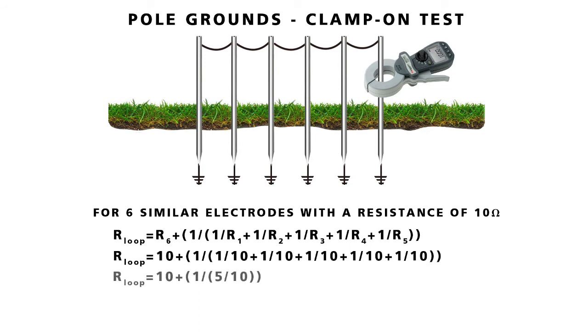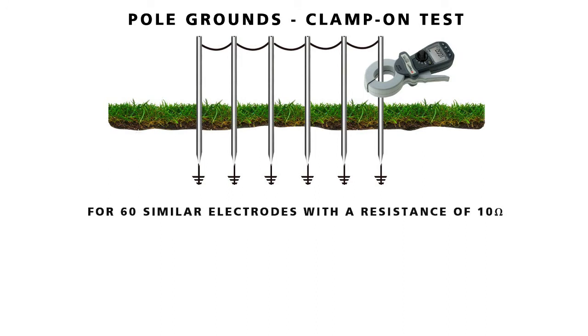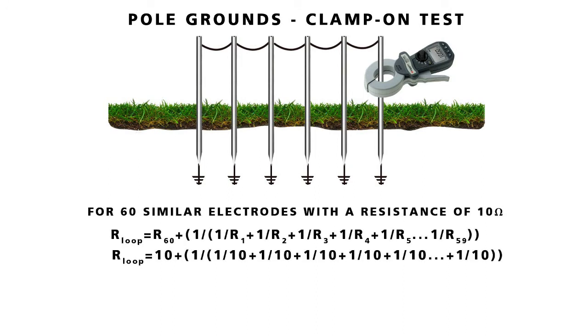In a 6-rod system, calculation shows the parallel resistance contributes 2 ohms and therefore a 10 ohm rod would read as 12. But for a 60-rod system, calculations show that the error is reduced to a mere .17 ohms.